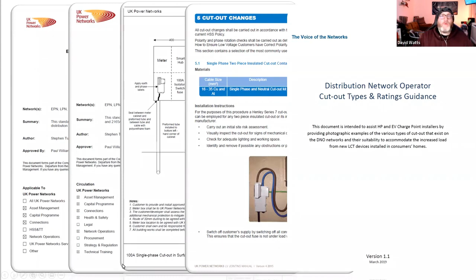Is there at all a mechanism where one network could have a special circumstance deviation from a generalized rule? Yeah, an example of that would be points within the SP Energy Networks network, where multiple points of earthing were done - we did that slightly different for the G12.4 standard, adding additional points into joints. So it's very important to refer to the ENA, but also the local power networks and their approach to things.